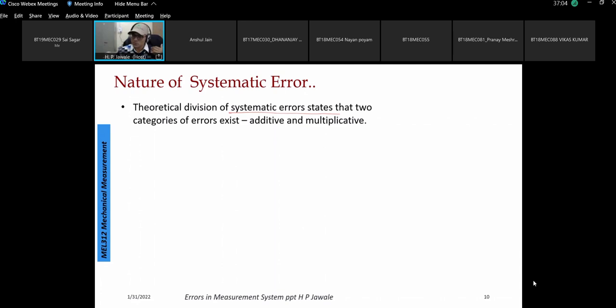So in relation to this, we must know what the nature of the systematic error is and how that is progressing, or how that is attributed or calculated as an error source afterwards in the measurement process. This is how you are going to calculate. Some equations are given in your practical, where you have to calculate the accuracy, full scale, true scale. You have to calculate bias, linearity, non-linearity, and other things. I think those are given to you. You need to understand that you have carried out the measurement process and you have got the measurement. Now let us understand whether there is some inaccuracy present in the equipment. Is it because of the systematic error? Right? That is our objective now. So through this objective, we will try to see the division.